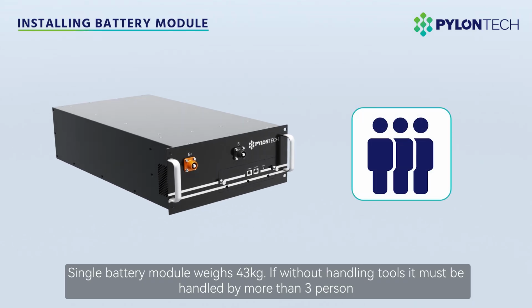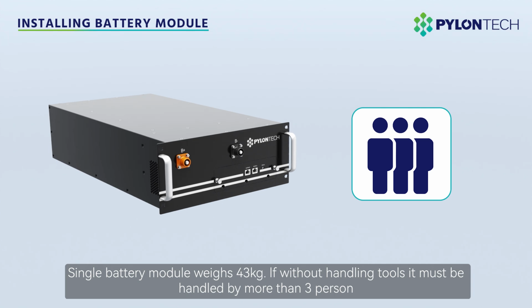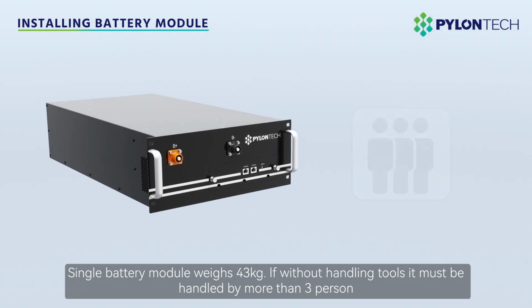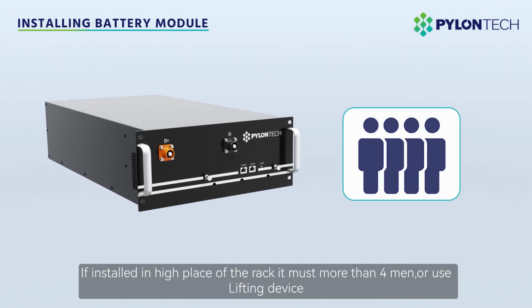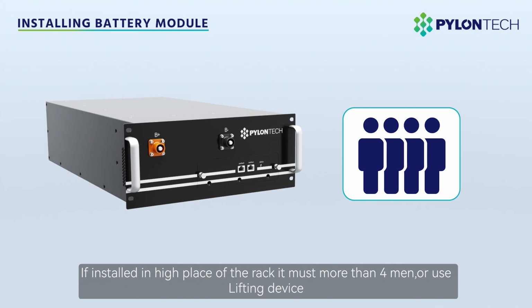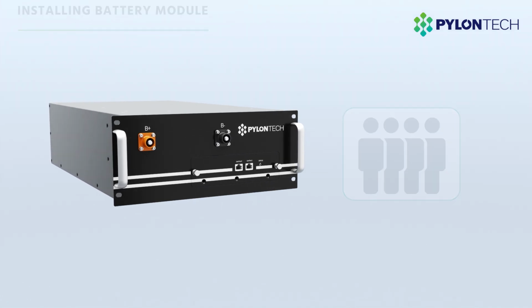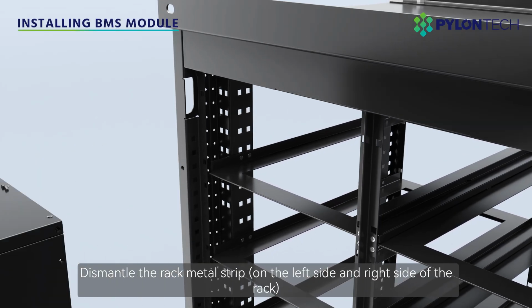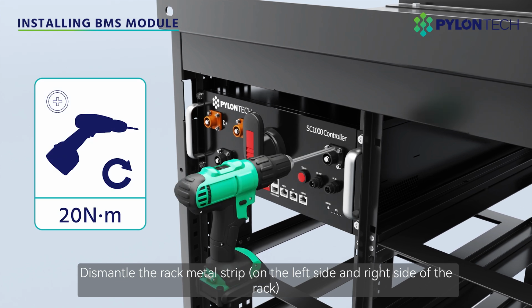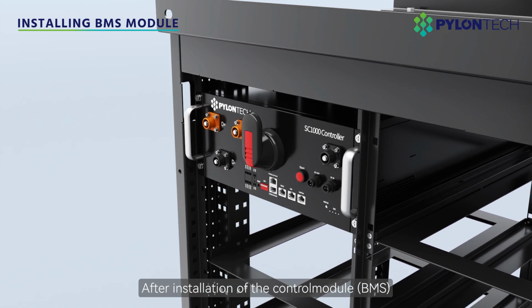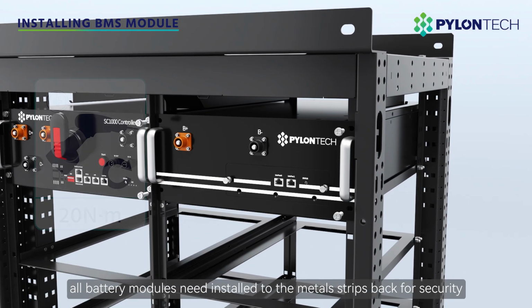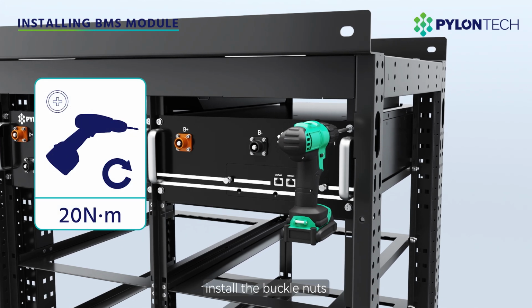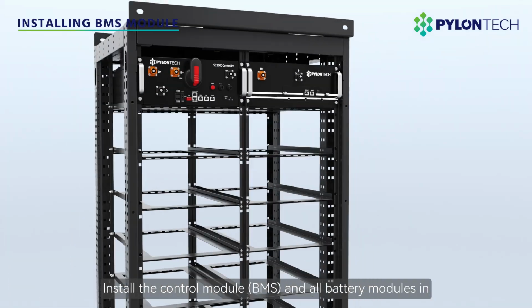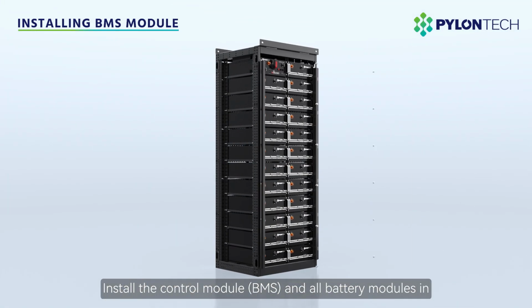Single battery module weighs 43 kilograms. If without handling tools, it must be handled by more than 3 persons. If installed in a high place off the rack, it must be more than 4 men, or use a lifting device. Dismantle the rack metal strip on the left side and right side of the rack. After installation of the control module, BMS, all battery modules need to be installed to the metal strips back for security. Install the buckle nuts. Install the control module, BMS, and all battery modules in.